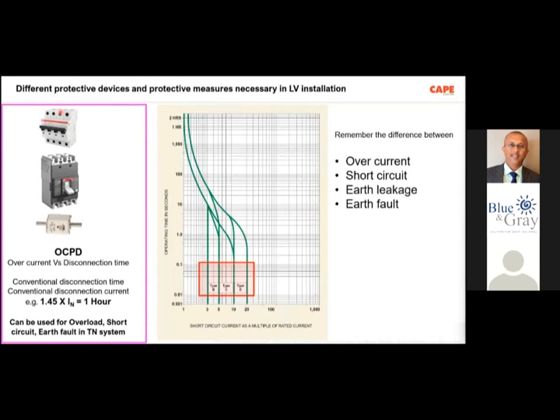Please understand that for fault protection, the primary protective device recommended is the OCPD. OCPD means the overcurrent protective device, which is nothing but a fuse or MCB or MCCB. This device is supposed to disconnect at the primary phase. Now, before going into that, you should understand that each of these devices has a disconnection curve. For example, you have a 10 amps MCB. If 11 amps comes, will it trip? Of course, no. For a 10 amps MCB, at 11 amps, the MCB will not trip.